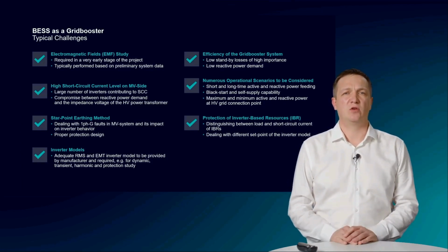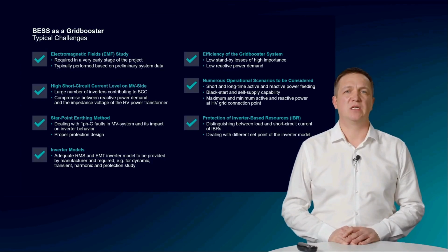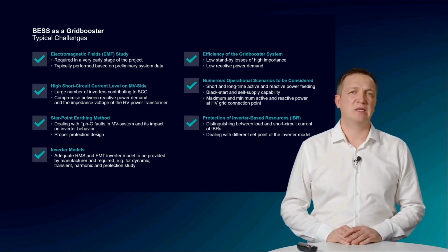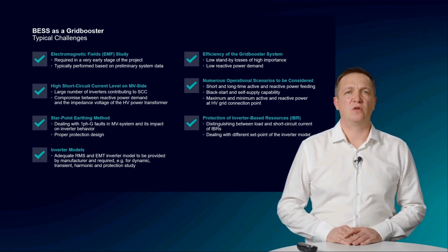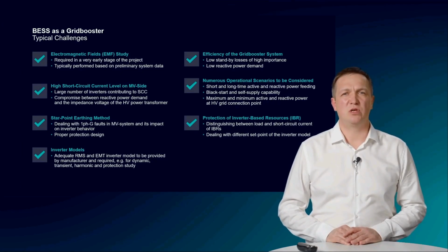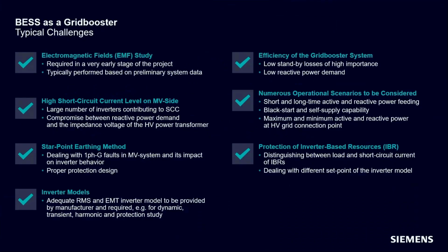When going for isolated operation, the single phase-to-ground faults are typically of a small amplitude and are not cleared instantaneously. The faults are indicated only using dedicated metering cores and sensitive protection functions. Following the indication, the faulty feeders are disconnected after some hours by the network operator. The challenge here is to check the selectivity, robustness, and reliability of the protection behavior based on transient simulations using proper inverter models. And this aspect brings me to the next challenge, namely the availability and parameterization of inverter models.